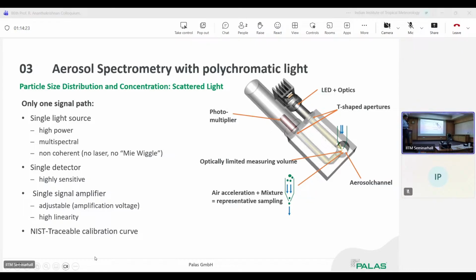Spectrometry with polychromatic light. All the sensors have more or less the same structure as the one you can see here. We have one light source, here in this case an LED light source. This is a more blue LED. Here in this device, it's a xenon light source, which is much brighter. Our sensor is equipped with a so-called T-shaped aperture on both sides. I will explain this a lot. We have one photomultiplier, which amplifies the signal coming from the scattered light, and we can increase or decrease the attenuation of that photomultiplier. And we measure in this area by focusing the aerosol stream, as you can see here, to the middle, and then the measurement.